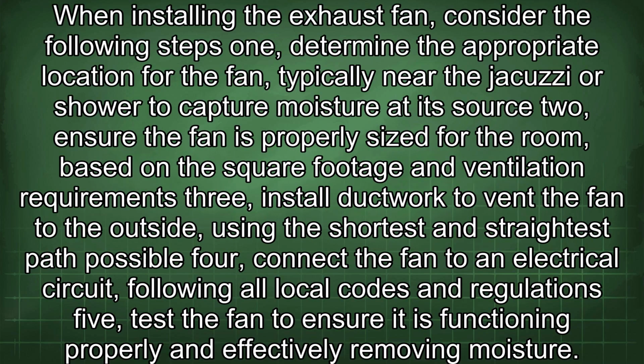When installing the exhaust fan, consider the following steps. 1. Determine the appropriate location for the fan, typically near the jacuzzi or shower, to capture moisture at its source. 2. Ensure the fan is properly sized for the room, based on the square footage and ventilation requirements. 3. Install ductwork to vent the fan to the outside, using the shortest and straightest path possible. 4. Connect the fan to an electrical circuit, following all local codes and regulations. 5. Test the fan to ensure it is functioning properly and effectively removing moisture.